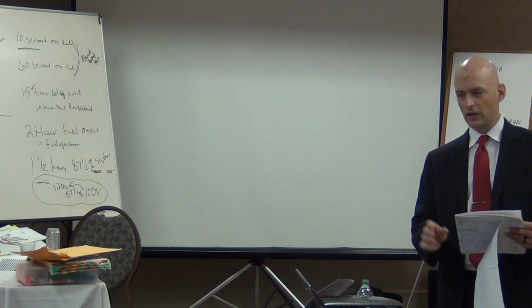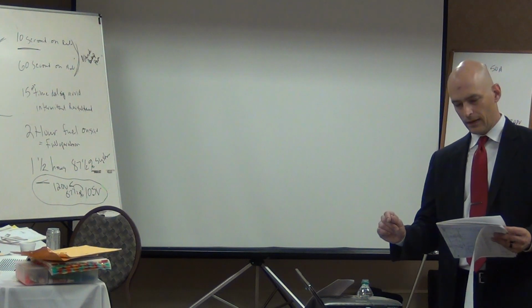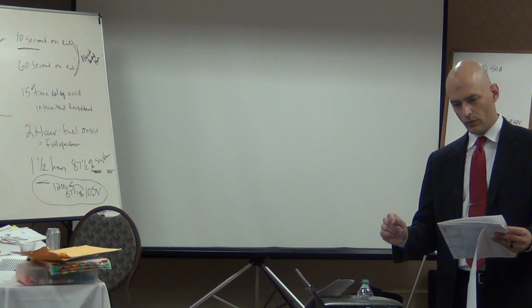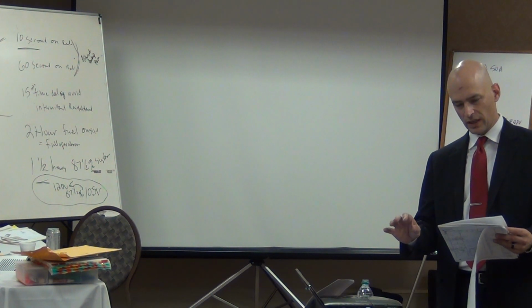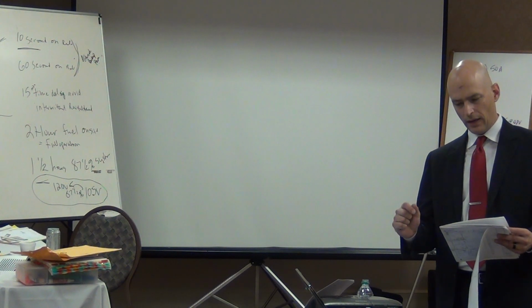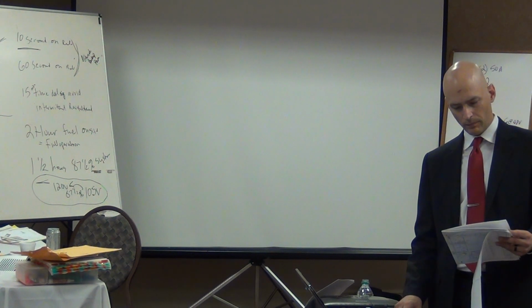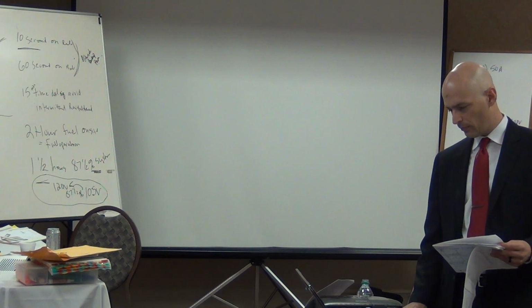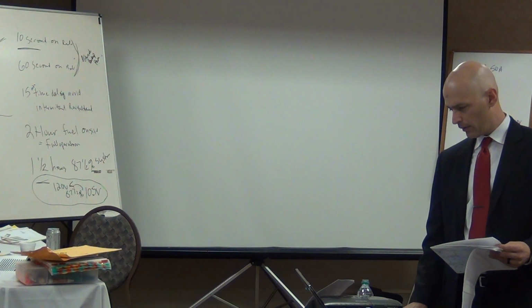So the mini substation itself is L1C, which is also the panel that's in the room. So it's L1C, that's the mini substation, and then you've got L1A, which is security fire alarm. The conductors that feed L1C are 2 number 8s and a number 10 ground with a single pole 40 amp breaker.